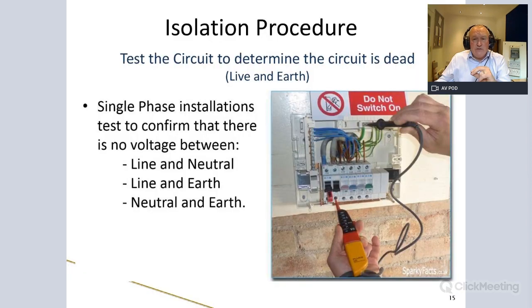Once we've tested the voltage indicator and know it's working, we can do the test procedure. For a single phase, we go between live and neutral, live and earth, and neutral and earth.